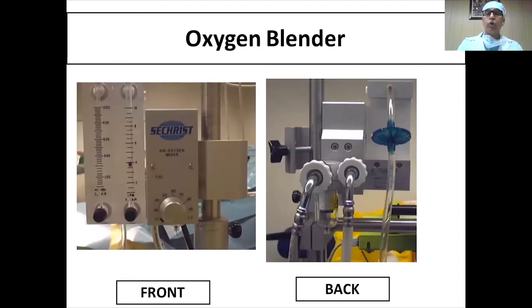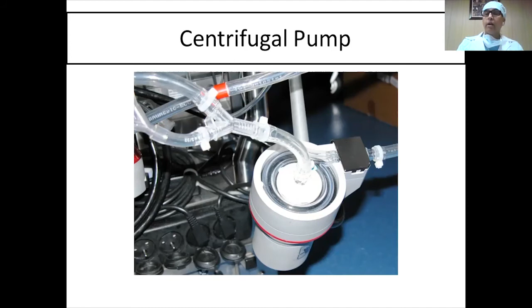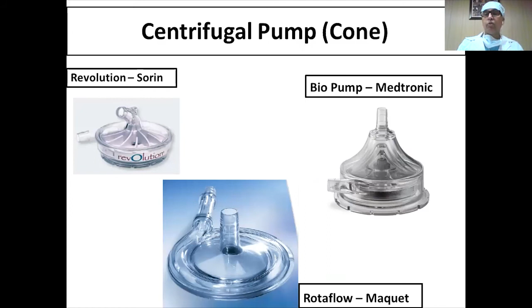This is basically the pump, a centrifugal pump, which is the heart of this machine. It runs, and with this it can create a negative pressure to draw the blood and push the blood forward to return it back to the patient. This pump head is supported by various motors. It can differ between companies, but the basic principles remain the same, though they have different priming volumes, which an intensivist or ECMO specialist should know.